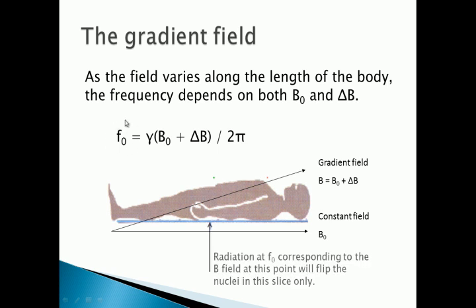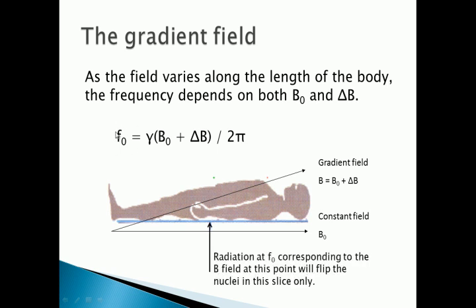The frequency that the protons are precessing at will depend on where in the body they are, because the magnetic field strength is varying across the body. When we apply a pulse of radio waves at a specific frequency F-naught — which is related to the magnetic field at a particular point in the body — only the protons at that particular slice will resonate, flip into the higher energy state, and start precessing. The others won't pick up the energy because they're not being driven at their natural frequency, so they don't resonate. Only those protons resonate, meaning you only get a signal from that particular part of the body.